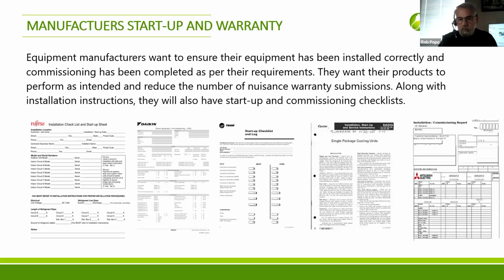As a consequence, manufacturers have startup checklists, and warranties tied to those checklists. Those startup checklists are not full commissioning, because manufacturers don't know all the performance targets of the job. They just want to make sure the refrigerant flows are correct, the amperage draws are correct, and all the things that make their equipment work are done.